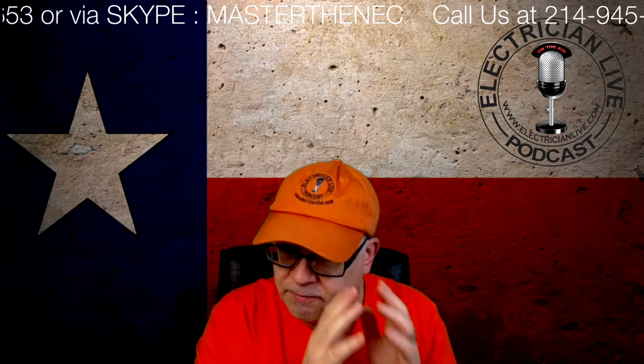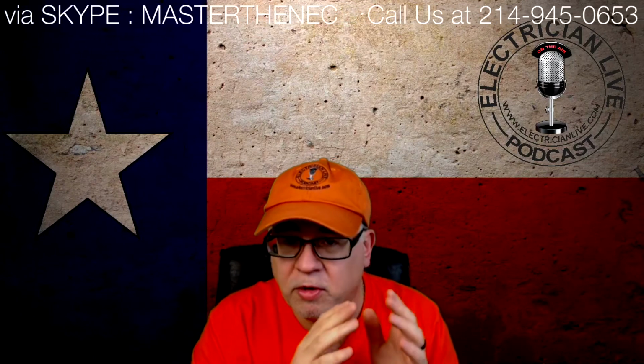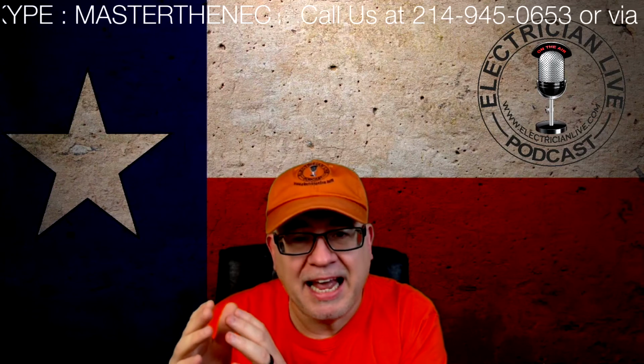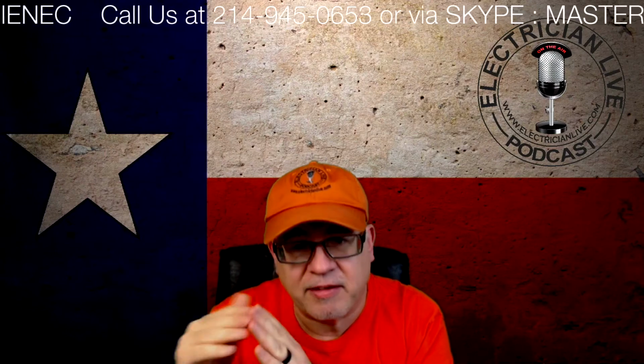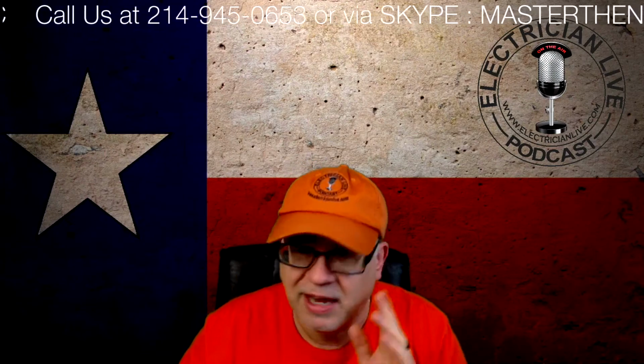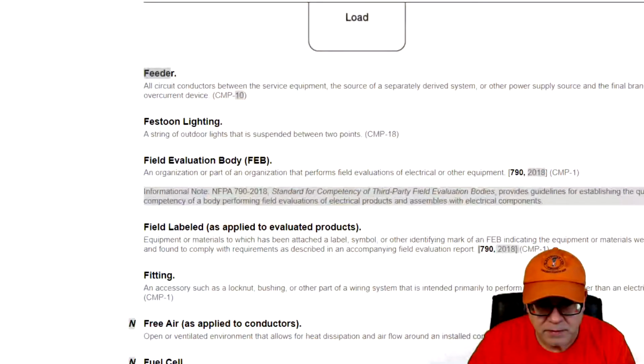Remember, feeder, from the service equipment or separately derived system to the last overcurrent protective device, branch circuit overcurrent protective device. And then from there, it's branch circuits out to things like receptacles, lights, whatever. I think you get it. All right, let's get back to it.